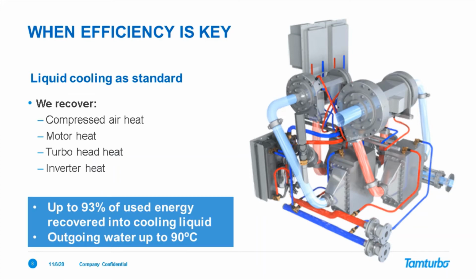And this slide is about efficiency in compression. As I explained, when there's no metal-to-metal contact, there are no losses because of bearings or anything else. Nothing else is affected by the spinning rotor and impeller other than air. So it's a very high efficiency rotation. It's also because of the precision that the air gap between the rotating impeller and the so-called volute, the turbo head, can be very small.